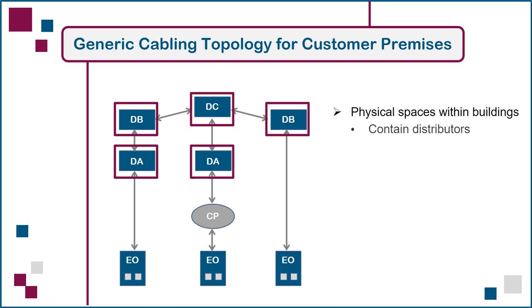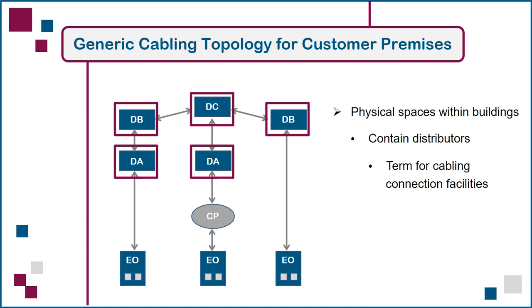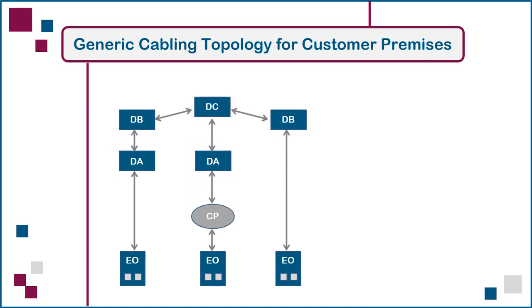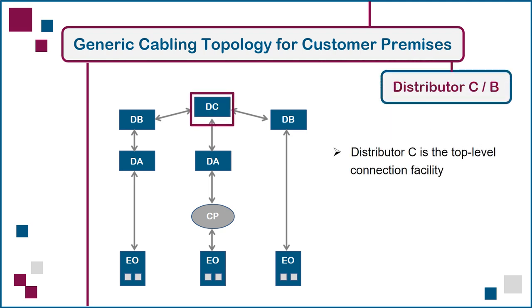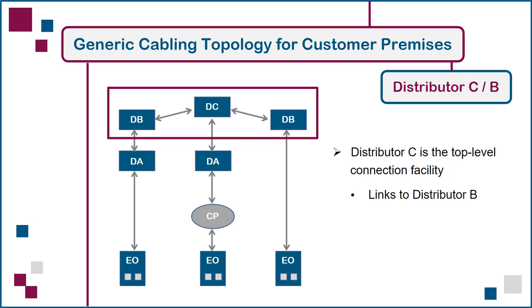These contain distributors, a term originally introduced in international standards publications to describe cabling connection facilities. If you have a campus, Distributor C would be the top-level connection facility in the main campus building, and it would have links to each Distributor B serving another building on the same campus. If you're not dealing with a campus, but instead, for example, a 100-storey office tower, you'd have the same setup, but the Distributor B's would be spread out vertically in your tower — for example, 20 floors apart, with Distributor C in the middle of the building on the 50th floor.